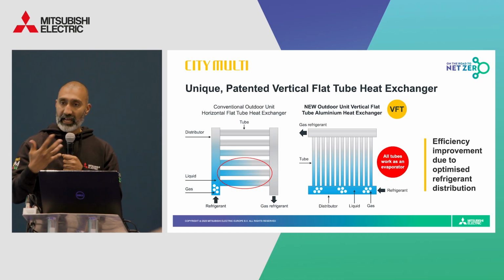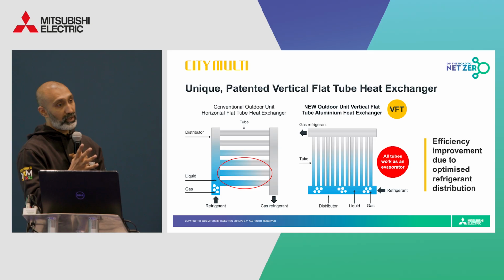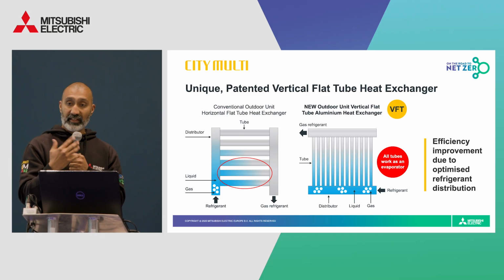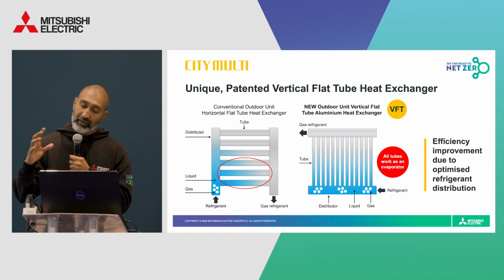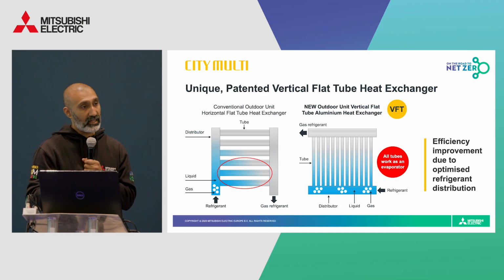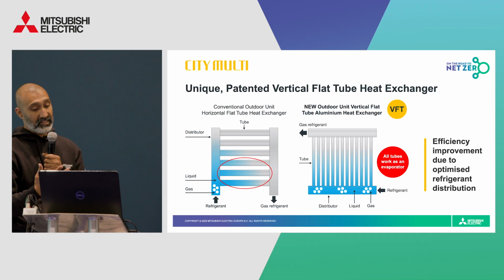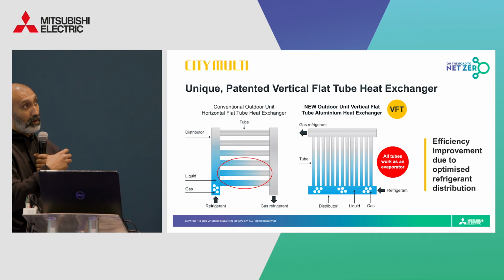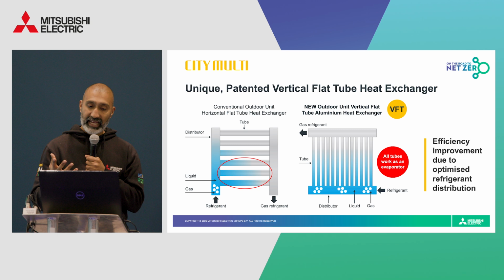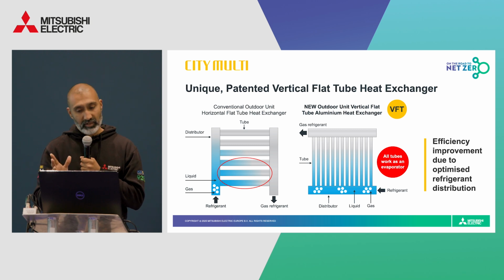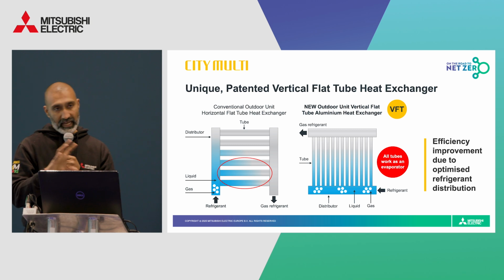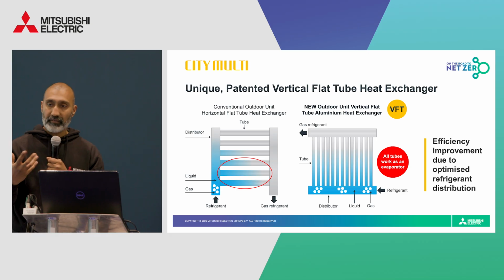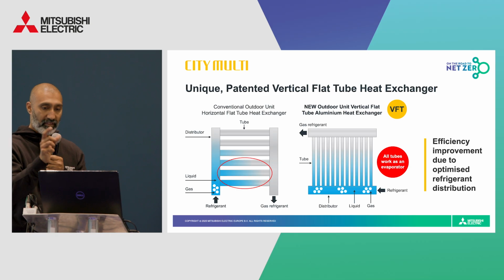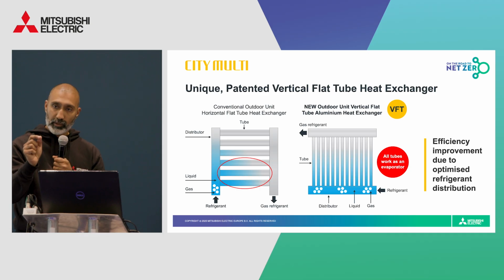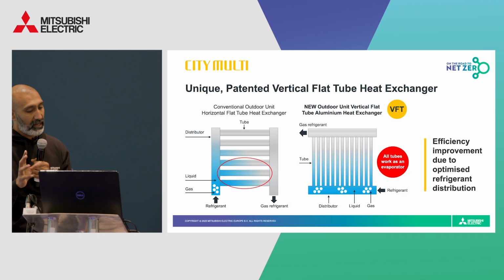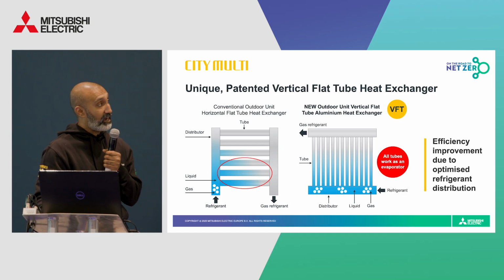Again, this time around, we have an efficiency improvement. So the outdoor unit is equipped with a newly designed heat exchanger that comes with aluminium flat tubes, but the flow of refrigerant from the main distributor is now done vertically. On the new heat exchanger, when the system is in full heating or majority heating, the mixture of liquid and gas is now directed from a horizontal distributor and fills the coil evenly, using every section of the heat exchanger and improving phase change. Additionally, more and thinner, closely packed tubes increase the heat exchanger surface area, improving the cooling efficiency through a higher density arrangement.